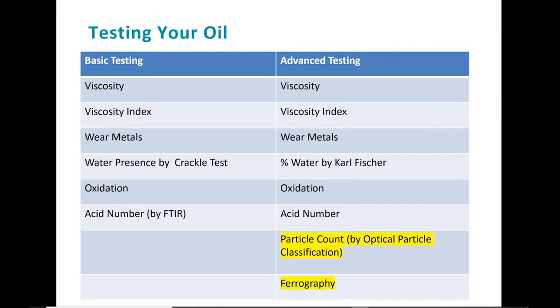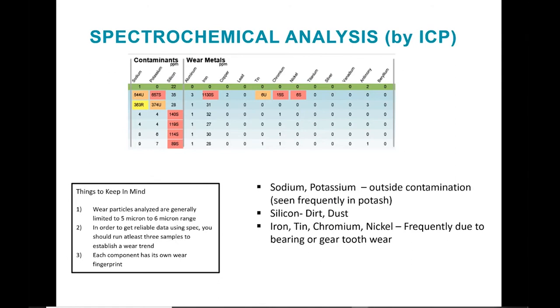Let's take a look at an analysis report, starting with the wear metal analysis as tested by ICP. A spectrochemical analysis measures the level of wear metals and concentration of additive elements, reported in ppm (parts per million), and provides an indication of the rates of wear of components and the depletion of additives. There are three things to keep in mind: wear particles analyzed are generally limited to 5 to 6 microns, which indicates particles as a result of wear but won't tell you the cause. You should run at least three samples to establish a wear trend, and each component has its own wear fingerprint. As you can see here, there's a high amount of iron, tin, chromium, and nickel wear, which can be indicative of bearing or gear tooth wear.